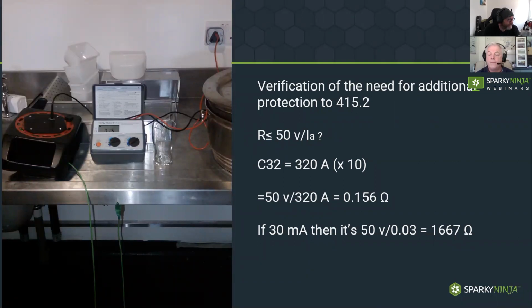Yeah, and if you want to determine if there are potentials, you get your R2 lead out - like I've done there, I've plugged the R2 adapter into the CPC of the socket and measured that to the exposed conductive parts, or the things you think may be exposed conductive parts. If you have a resistance value, it means there's a potential there that under a fault condition from the source of energy - in this case a socket, but whatever the equipment is - you find out what the value of current could be in a fault condition, which is the maximum required to achieve disconnection time.